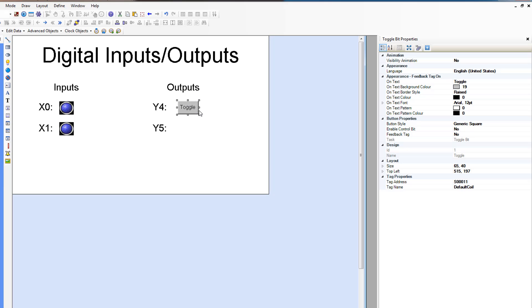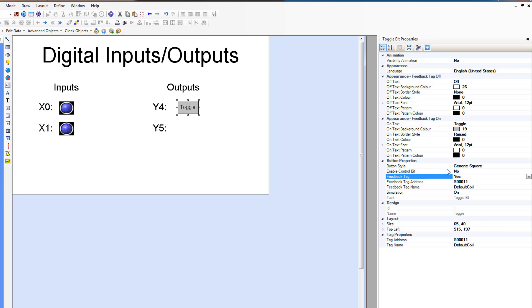This toggle button will toggle whatever tag address you associate with it. But by default, it's not going to change appearance. So we're going to turn on the feedback. We're going to allow a feedback tag to be specified so that it will change the appearance so it'll be either off or on.